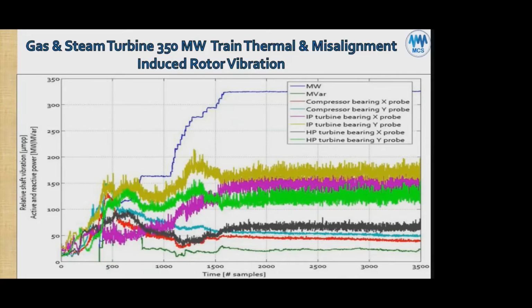Why? Casing vibration is great for judging the amount of axial misalignment occurring, because you end up with a high axial vibration on the casings when you have misalignment. It's a very good indicator. The axial vibration should never exceed 50% of the radial vibration measured using seismic probes on the bearing housings. If it's exceeding 50%, you definitely have an axial vibration that's typically caused by misalignment, although it could also be resonances somewhere in the supports. Rarely it can be resonances in the supports, but typically it's misalignment. So why do I talk about misalignment here?